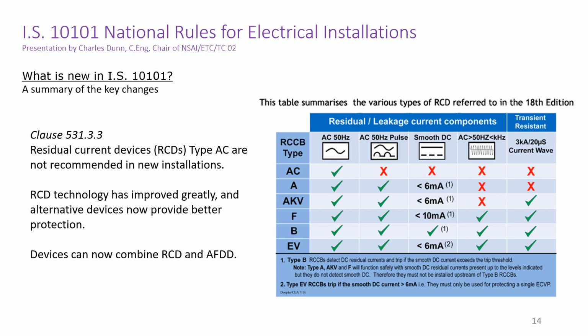Clause 531.3.3 states that residual current devices, RCDs, type AC, are not recommended in new installations, but the new clause stops short of asking for the old type AC to be removed from all existing installations. Now, this is a worry because we know that the old AC type can sometimes be blinded and not operate on earth fault. Replacing all existing RCDs throughout the country would be a huge task though, and at the moment the new regulation only advises against the use of AC type in new installations. It is a good idea though to replace any old AC type RCDs if you are rewiring an installation.